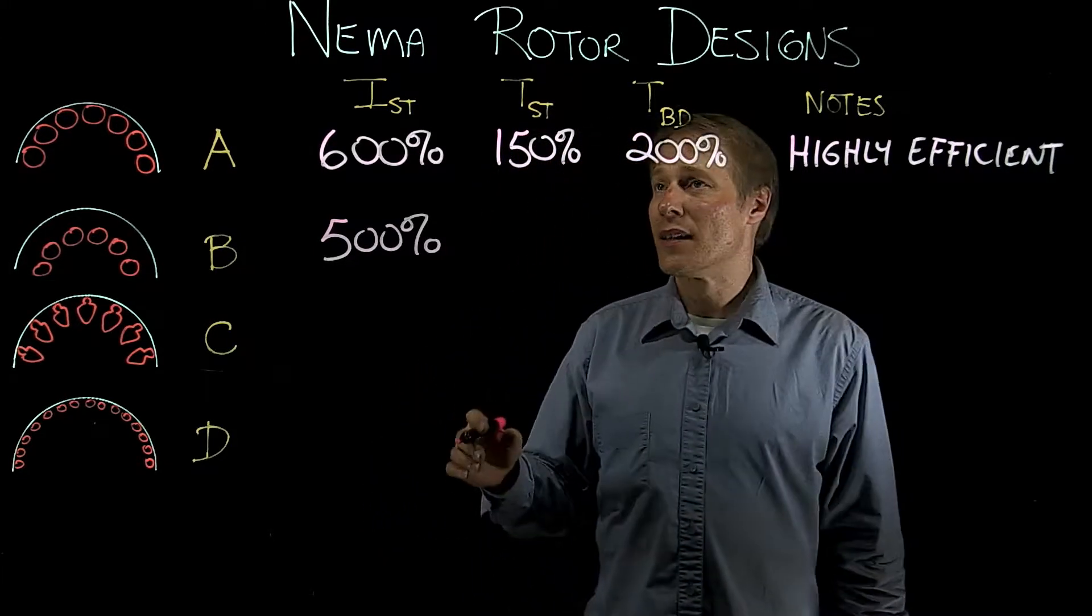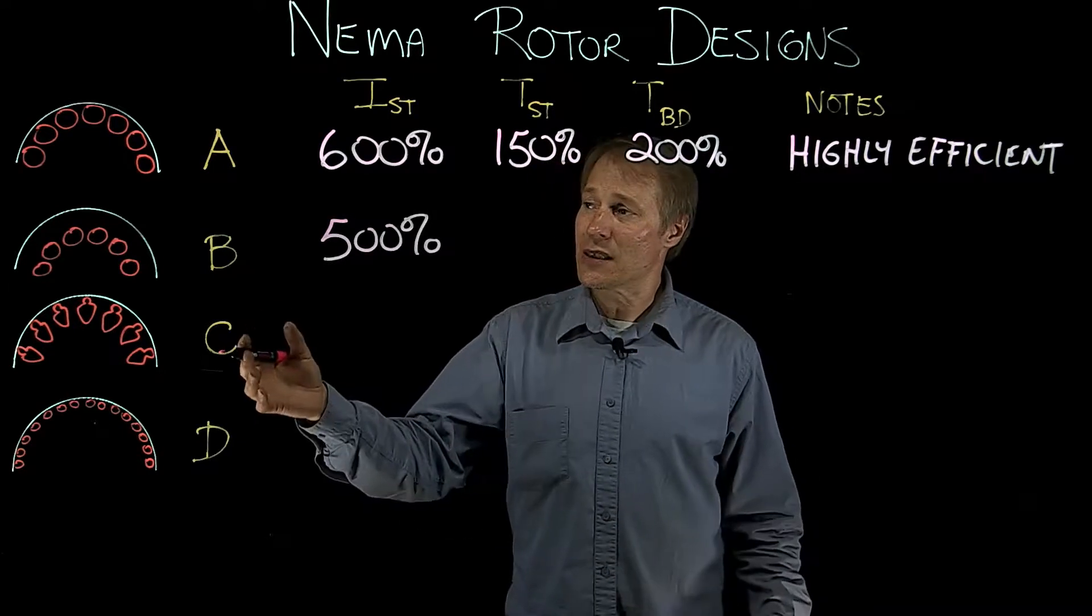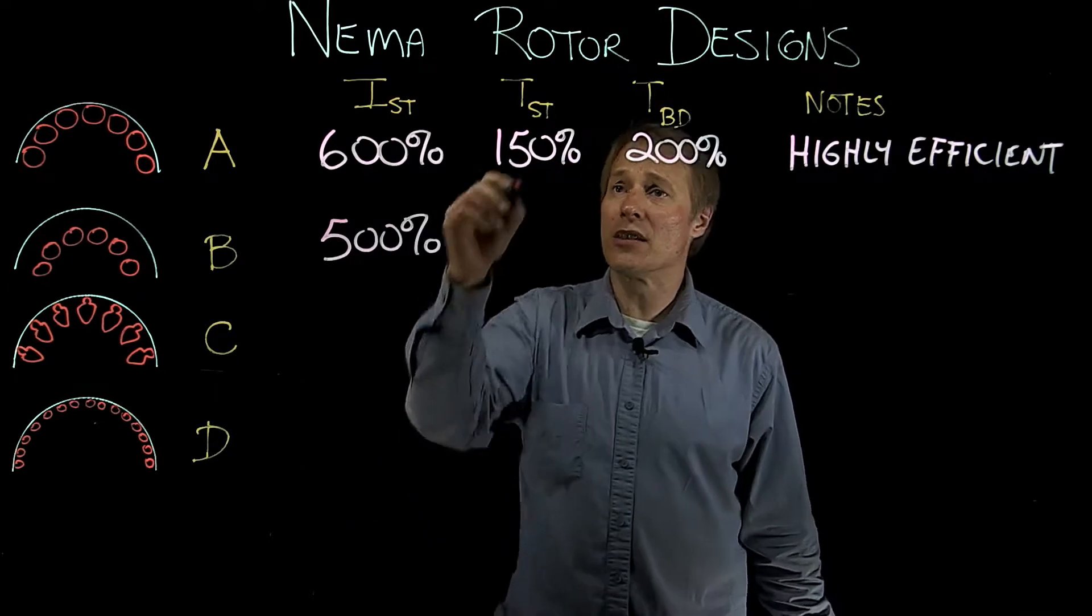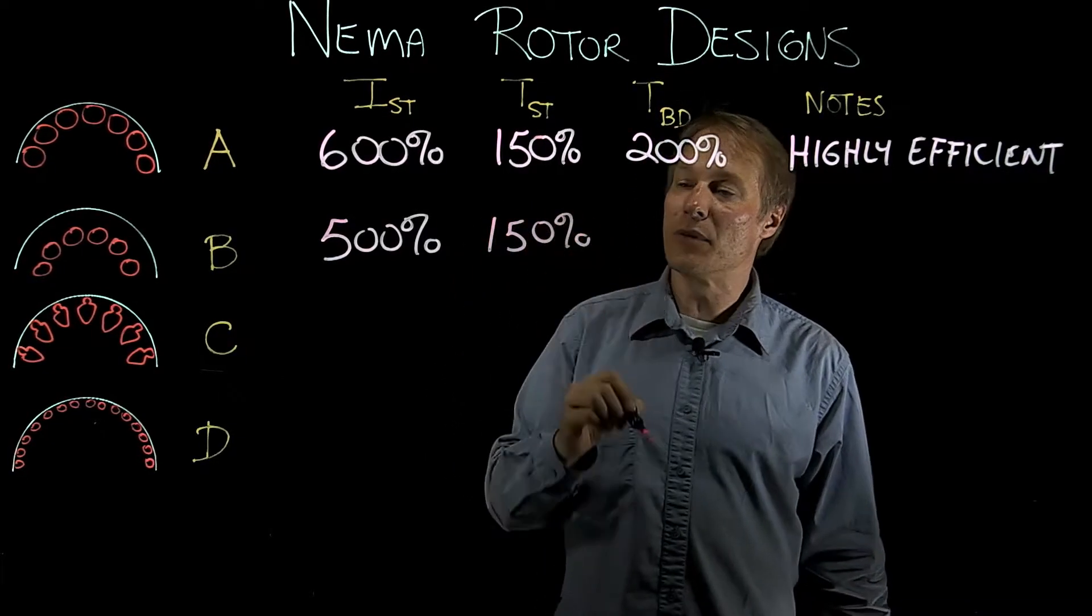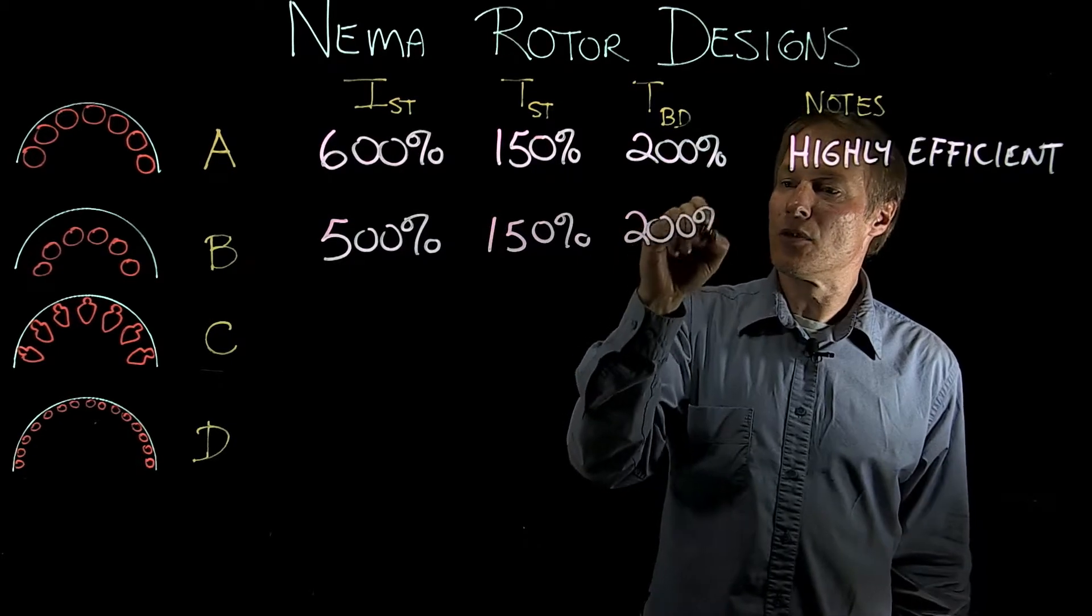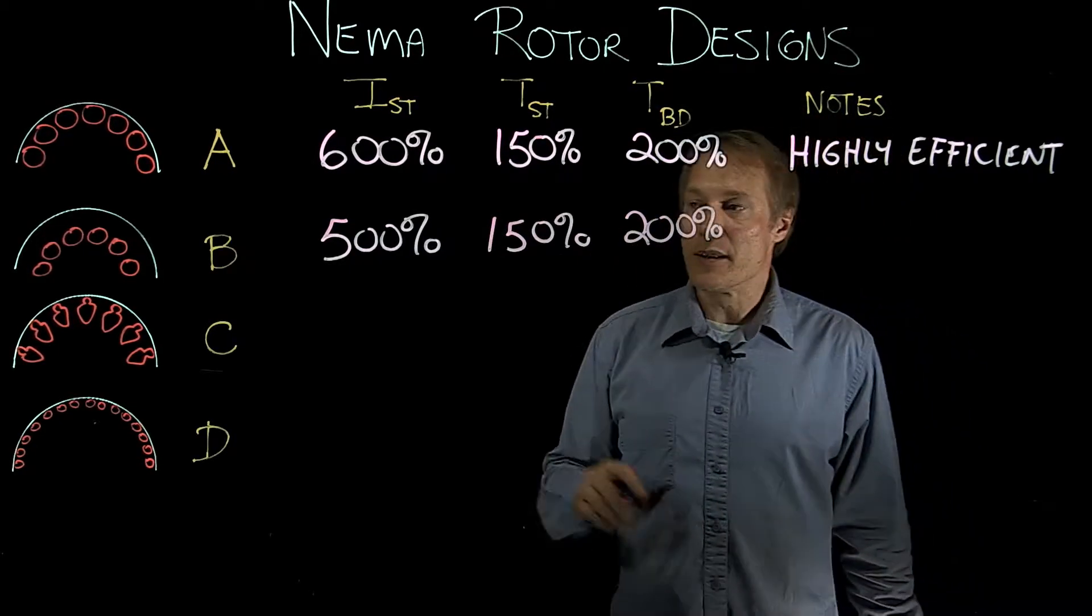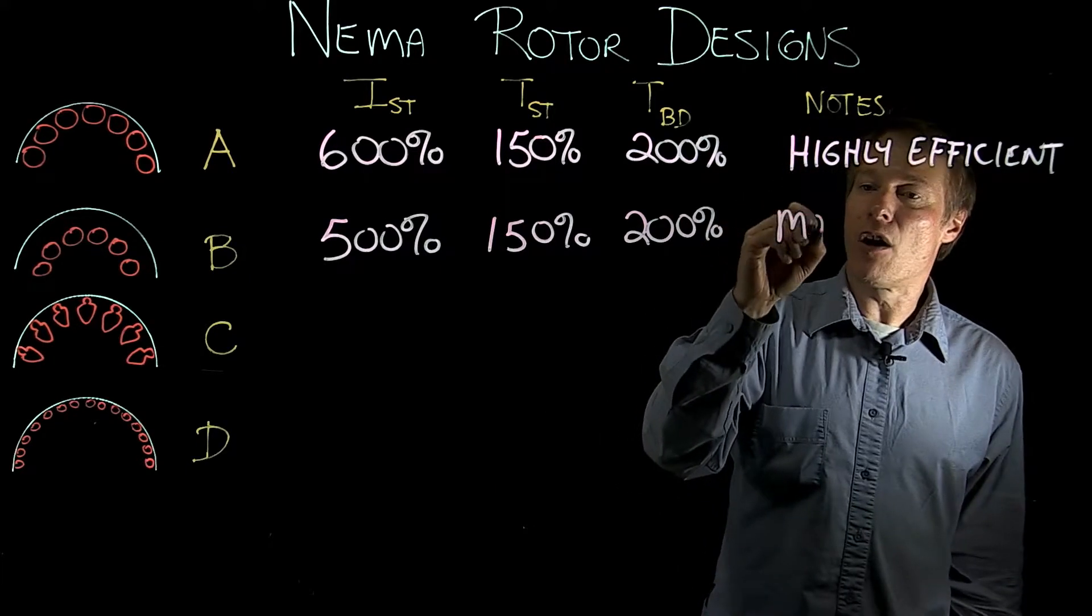Now the starting torque, that's dependent upon the in-phase current. Well the resistance isn't changing, so the in-phase current doesn't change. So it's also going to be 150%, and the breakdown torque is going to stay the same too, at 200%. The main characteristic of this rotor is it is the most common rotor.